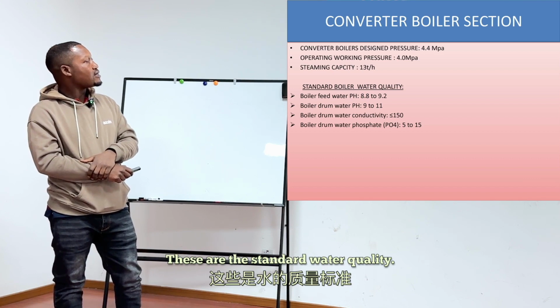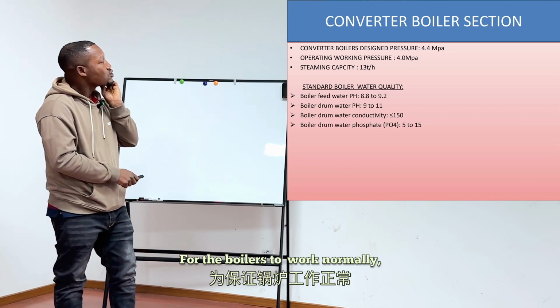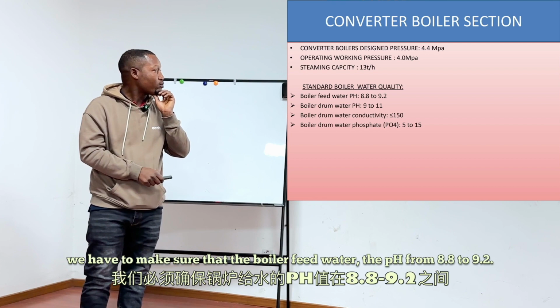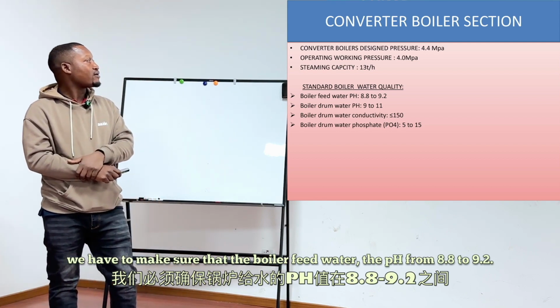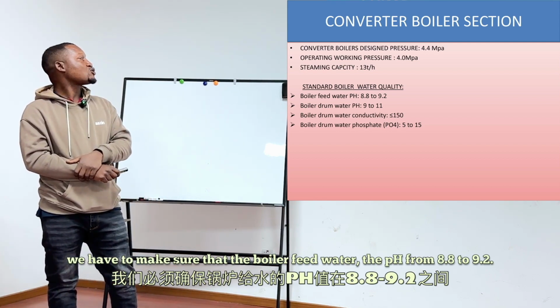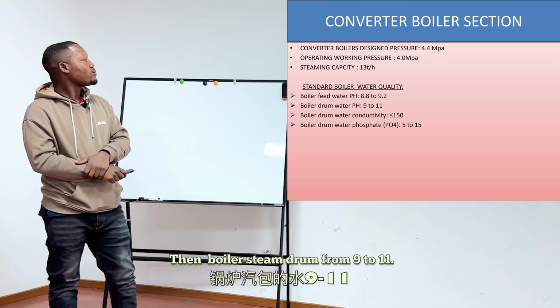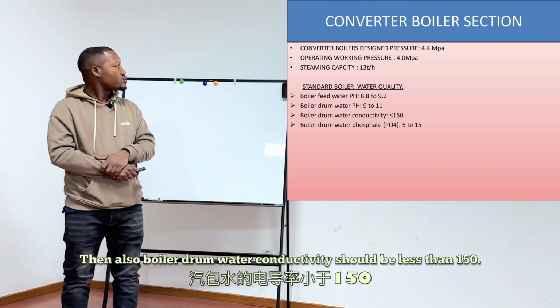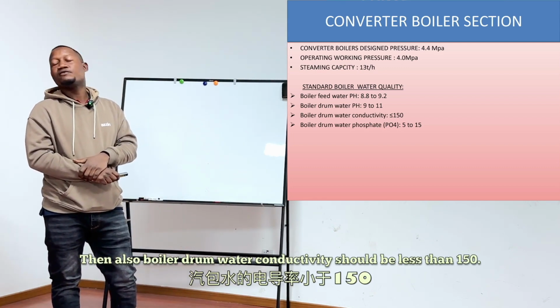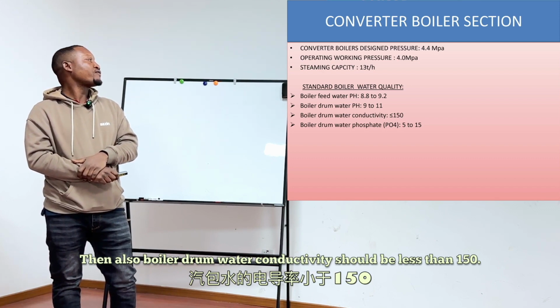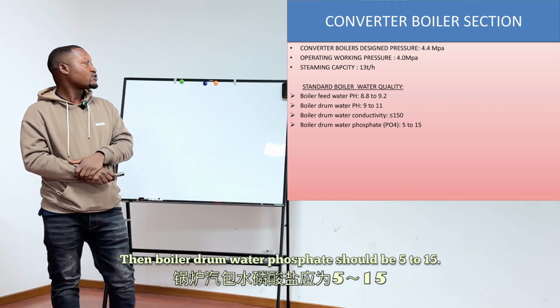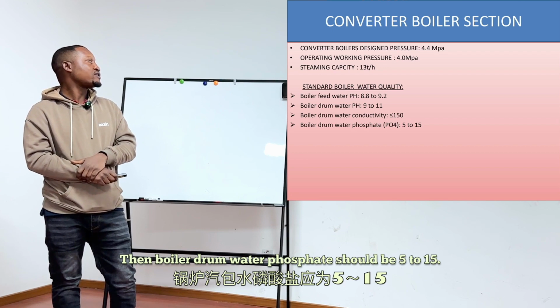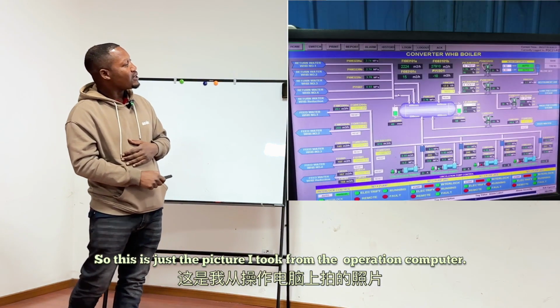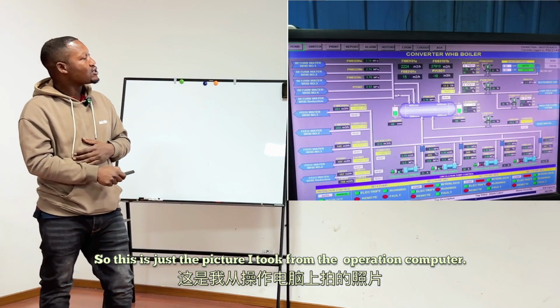These are the standard water quality values. For the boilers to work normally, we have to make sure that the boiler feed water pH is from 8.8 to 9.2. The boiler steam drum pH is from 9 to 11. The boiler drum water conductivity should be less than 150. The boiler drum water phosphate should be 5 to 15. This is a picture I took from the operation computer.